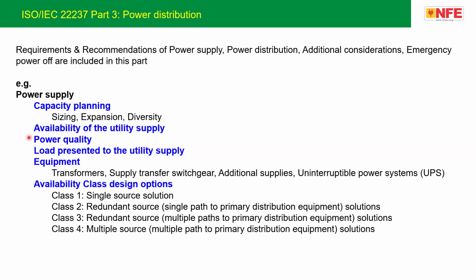When we go for power quality, we should also take care. Power quality plays a critical role in the data center because we are feeding the IT rack. If we go for power quality monitoring, the data should be properly logged, analyzed, and collected according to the IEC requirement. And regarding the load presented to the utility supply, the load power factor and the harmonics presented to the supply shall remain within the boundaries. They should not go beyond the IEC requirement and IEEE requirement.